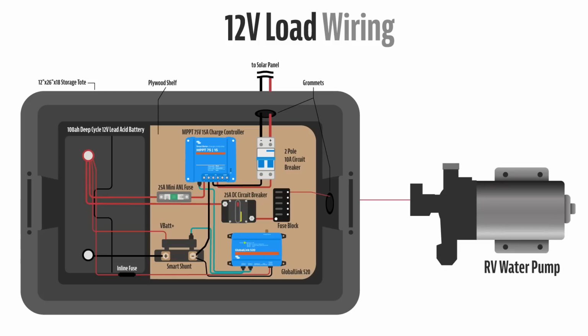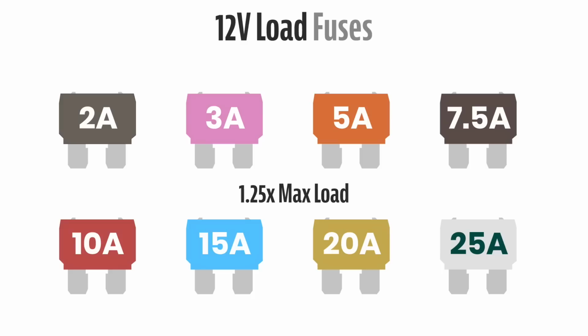Now that the main system is connected, it's time to add your loads. From a high level, you'll take the positive wire from your item into the load center and fuse it appropriately. The blade fuse should be roughly 1.25 times the max amperage that item will draw.